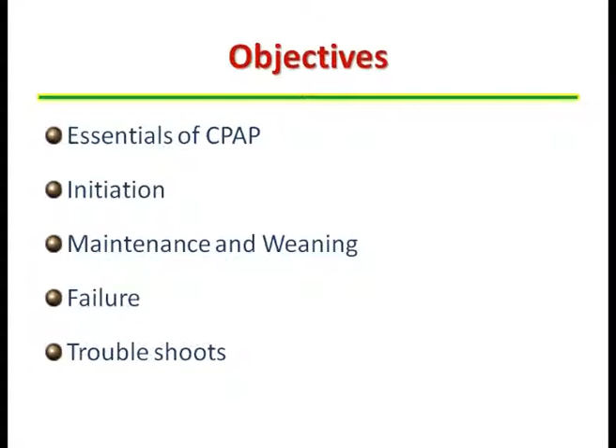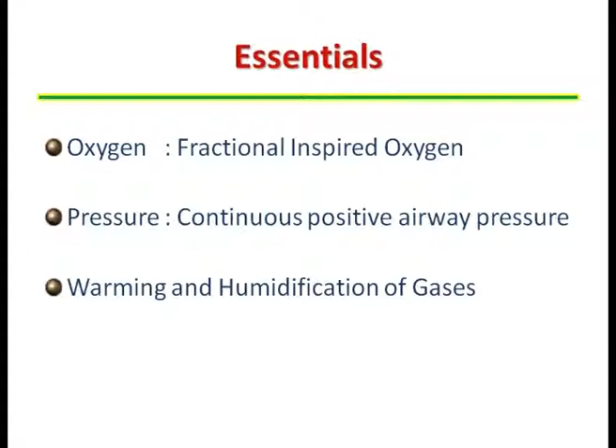Coming to the essentials of continuous positive airway pressure, when we say a baby is on bubble CPAP, we mean the baby is getting oxygen and pressure with a warm and humidified gas. These gases are air-oxygen mixtures. Oxygen which we give is given as fractional inspired oxygen concentration in the range of 21 to 60%, and the pressure is delivered to maintain functional residual capacity, and the pressure ranges are between 4 to 7 centimeters of water. Gases are delivered at a temperature of 37 degrees Celsius with a relative humidity of 100% when they reach the nares of the baby.